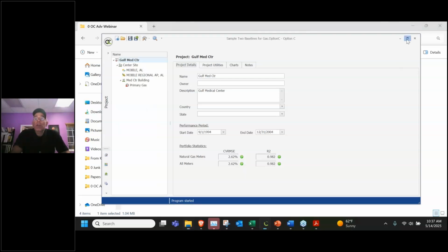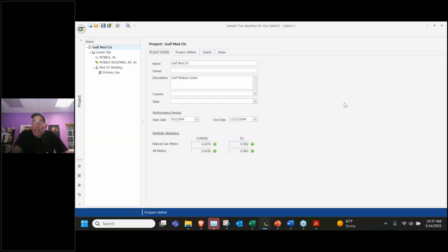There is another way of doing M&V using utility bills, and that is where you do a regression of before and after. So you get 12 months of data before, do a regression. You get 12 months of data after, do a regression, and apply both regressions to TMY average weather data. And that will show you if you saved anything.